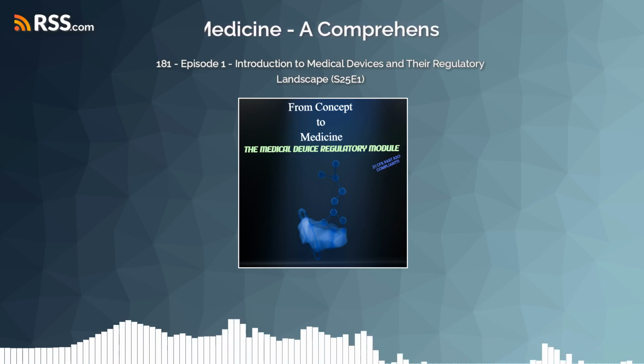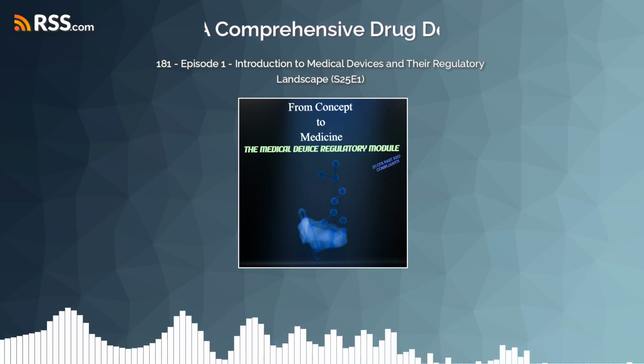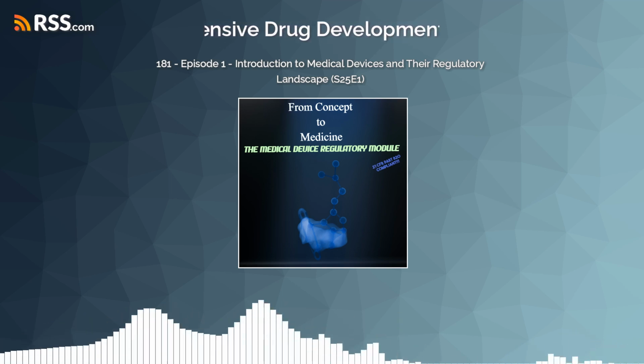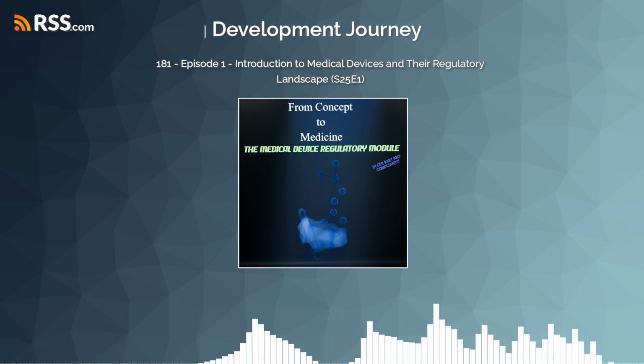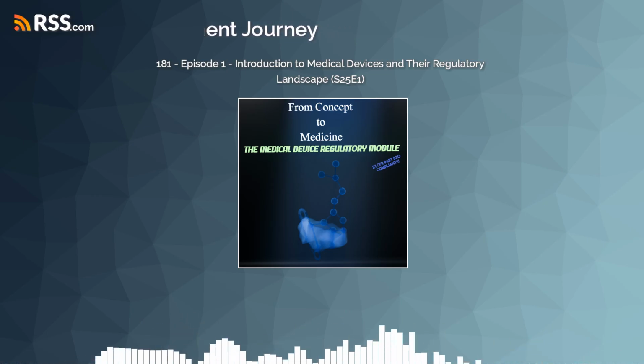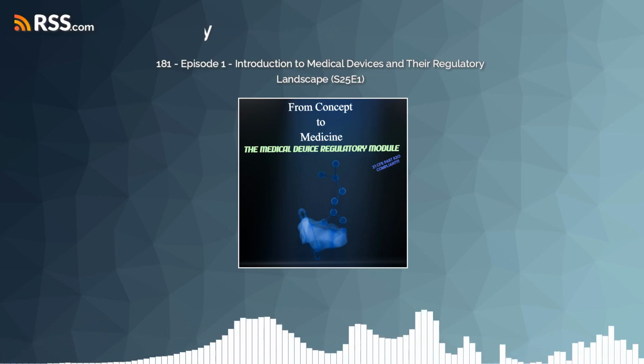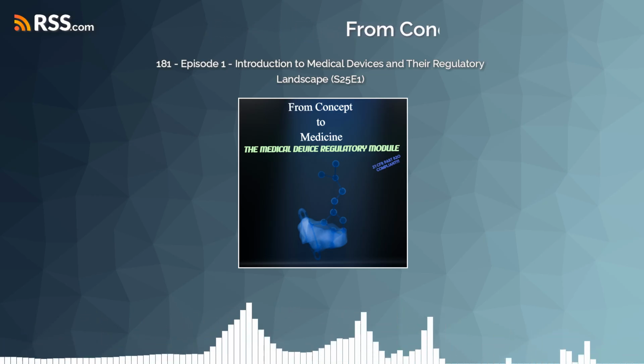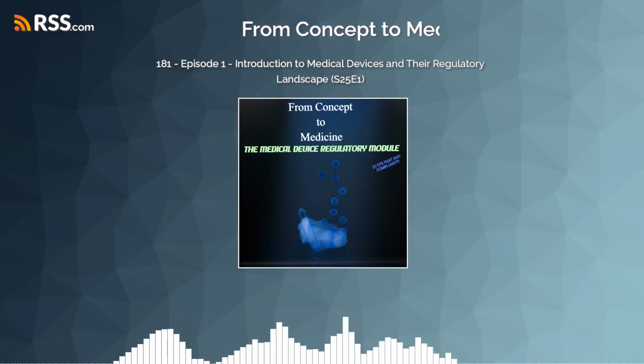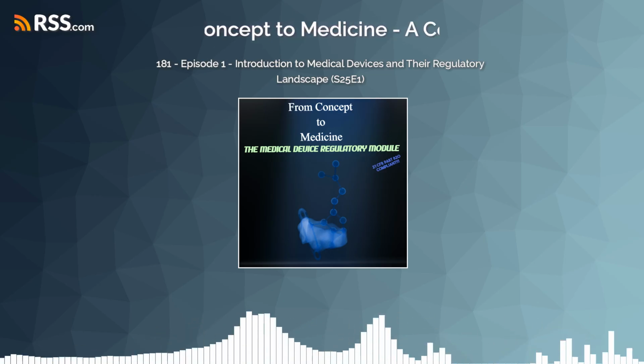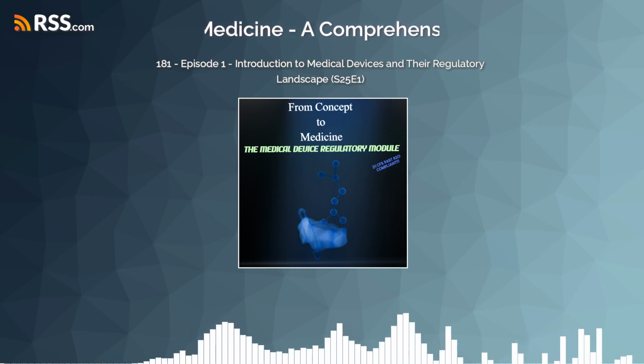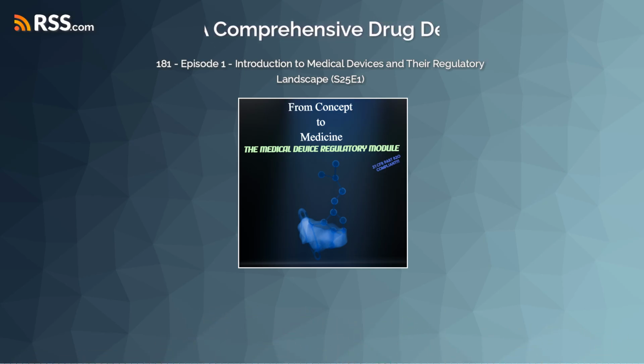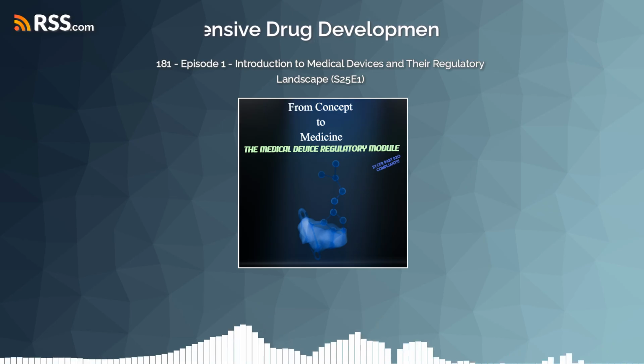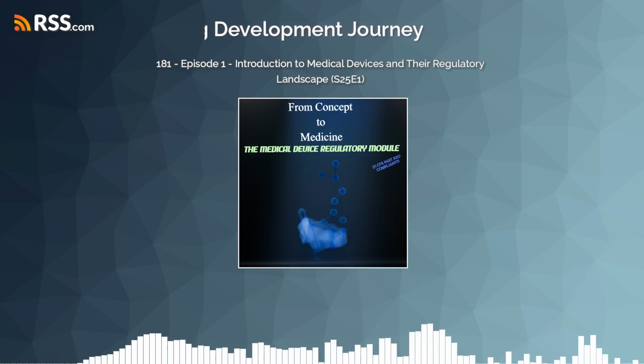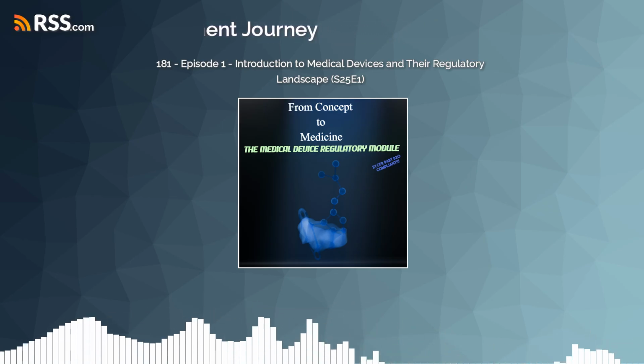So what's the pre-market submission for Class 3? I'm guessing it's the most stringent, demanding a huge amount of data. Absolutely. Most Class 3 devices require pre-market approval, or PMA. A PMA application involves the most stringent scientific and regulatory review by the FDA. It requires comprehensive data: non-clinical laboratory studies, animal studies, and crucially, clinical investigations involving human subjects to demonstrate safety and effectiveness. So extensive clinical data is usually a must.